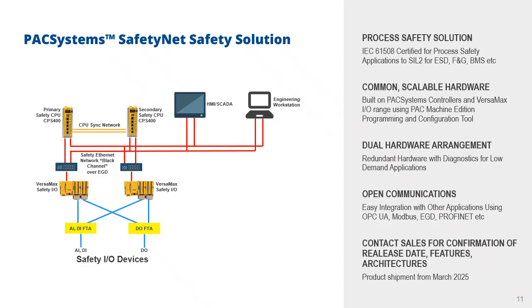So this is the PACSystems SafetyNet safety solution. It's a process safety solution certified to IEC 61508, and it's suitable for process safety applications to SIL2, including ESD, fire and gas, burner management systems, and others. This is based on our existing PACSystems controllers and Versamax I/O ranges, and we're using our PAC Machine Edition programming and control software in order to have a lot of family commonality with existing PACSystems ranges.